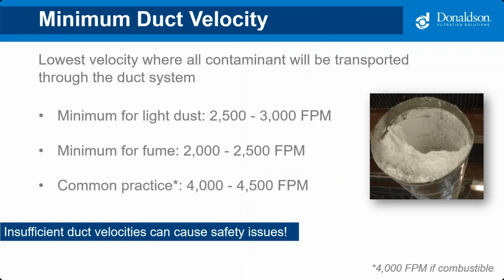The minimum duct velocity is a critical design factor. It is the lowest velocity where all contaminant will be transported through the duct system. If you go below this velocity, dust could settle out within the ducts and cause other safety issues. Duct lines, no matter the size, must be full of air at the design conveying velocity to avoid settling out. This picture is definitely not what you want to see.